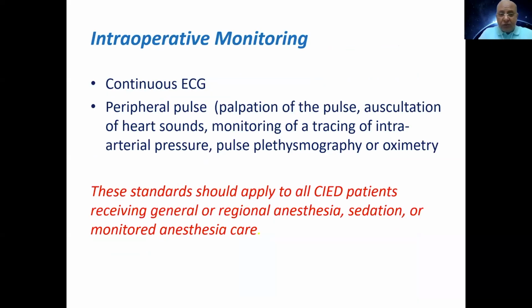ECG alone is not enough. You have to do peripheral pulse monitoring. Very important, because, as I said before, the spikes may be counted by the monitor as if the rate is 70 while the patient is in asystole. So you have to do peripheral monitoring of that.